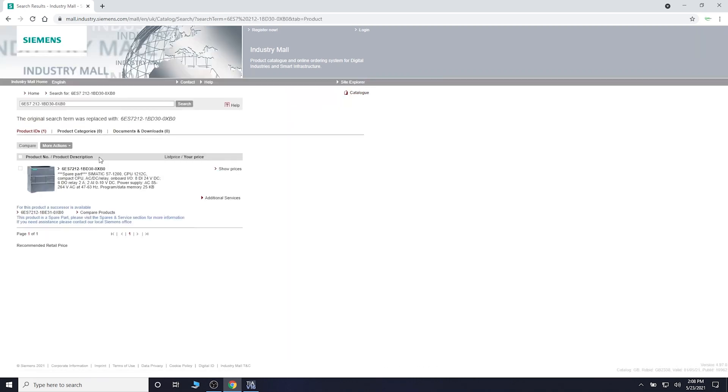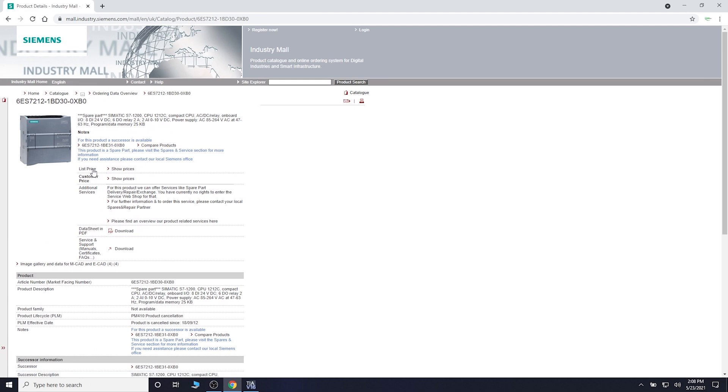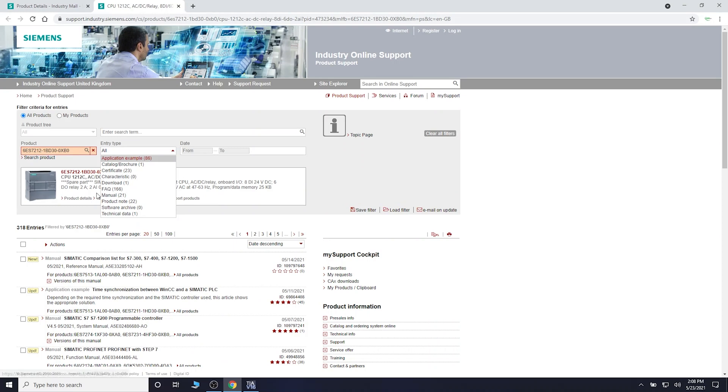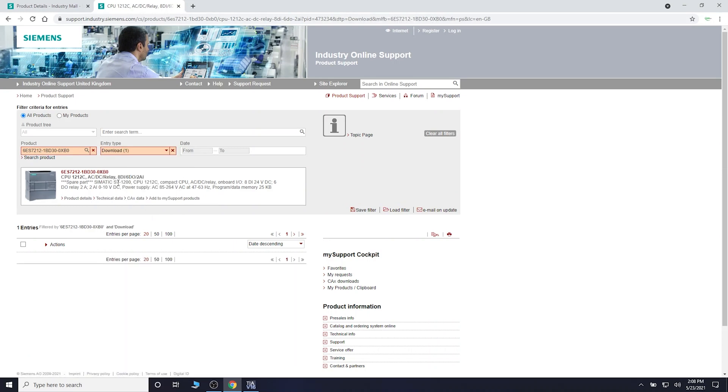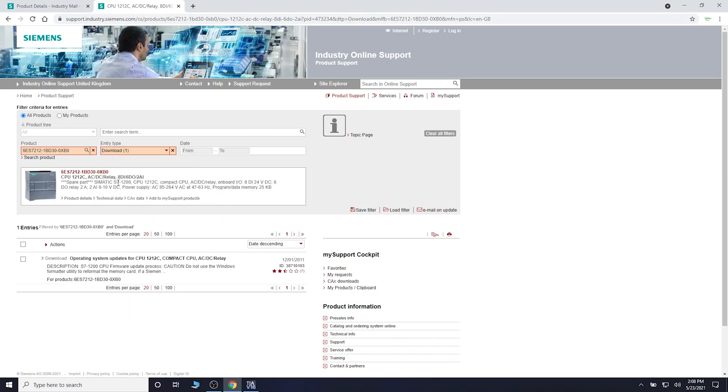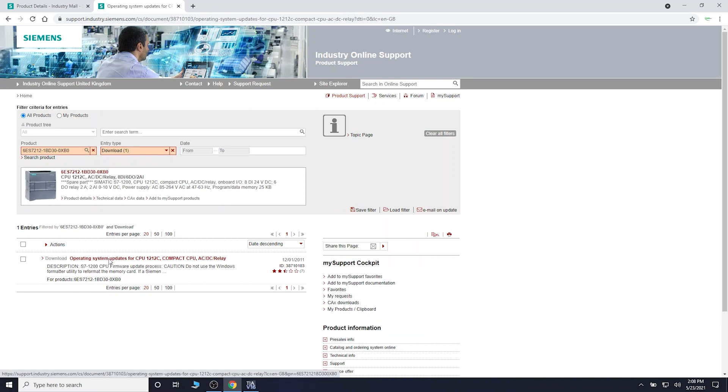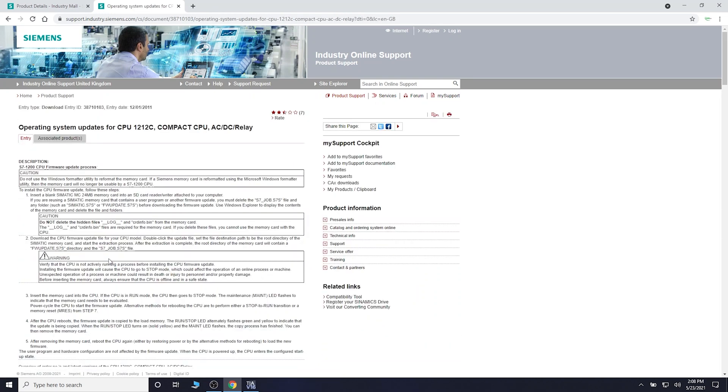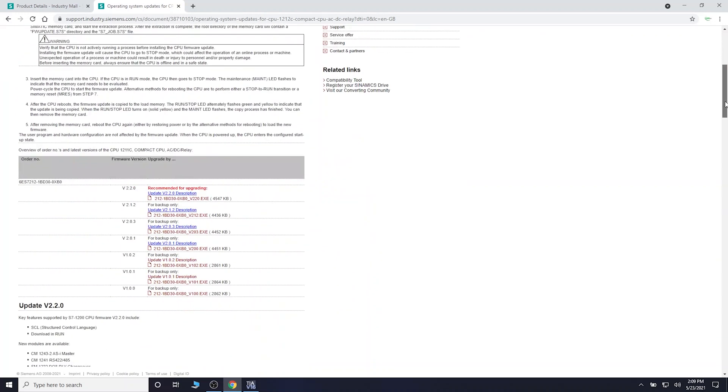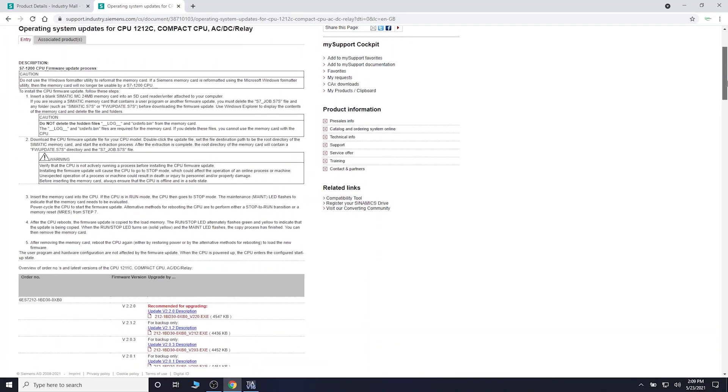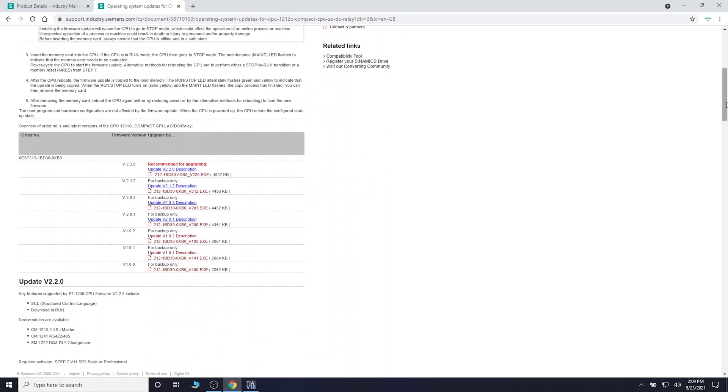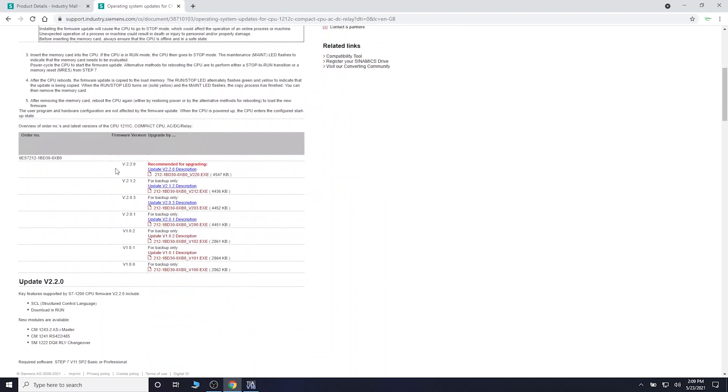Use product search. Once you find your controller, go into the controller itself, then go into downloads and services. Go into the downloads section. As you can see, there's operating system for CPU 1212C. It shows you all the descriptions, how to update your firmware and things like that. Here it's showing you the last firmware that was available for this controller. Just click download. Make sure you're registered and approved by Siemens to do that.